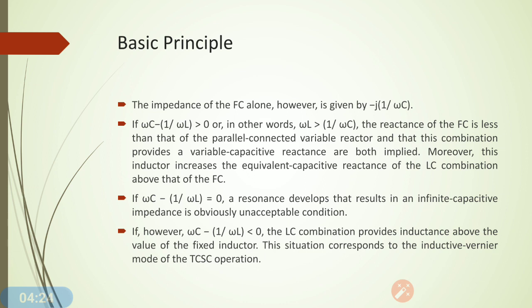The second condition is when both the capacitive value and the inductive value are equal. In this condition, resonance will develop and this condition is not acceptable at any cost. The third condition is when the LC combination provides inductance above the value of the fixed capacitor. This situation corresponds to the inductive vernier mode of TCSC operation.